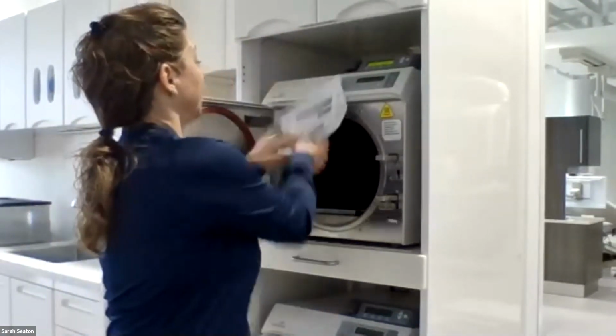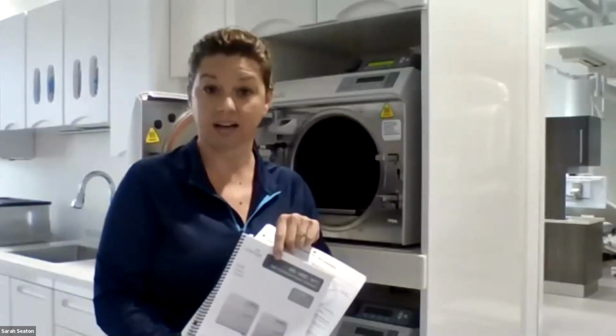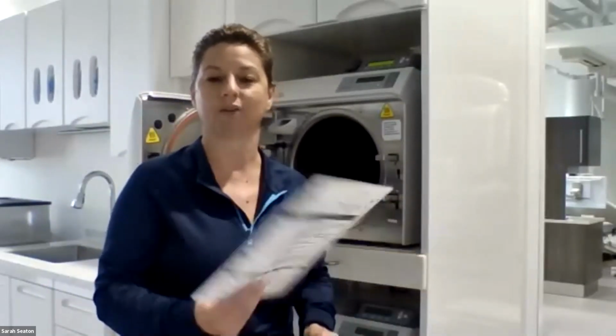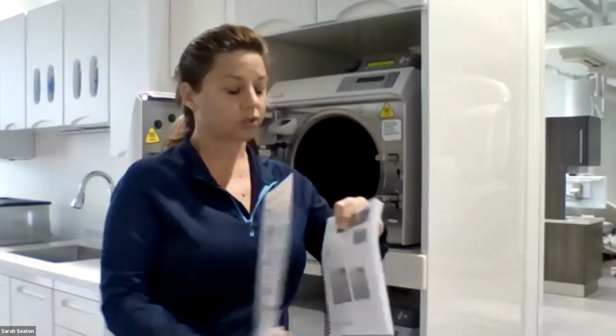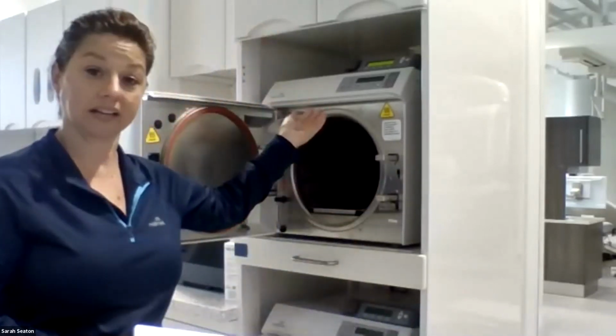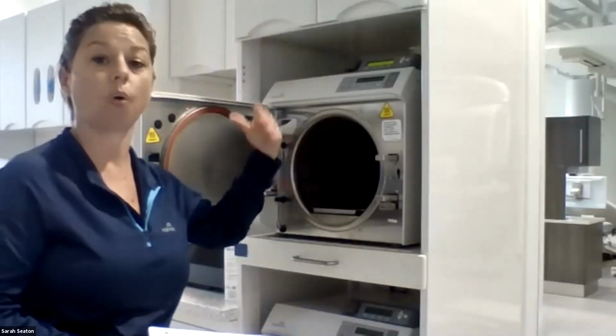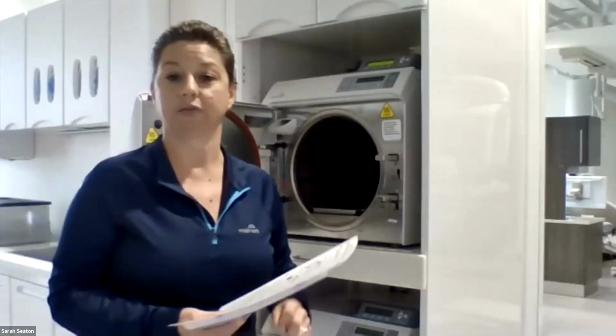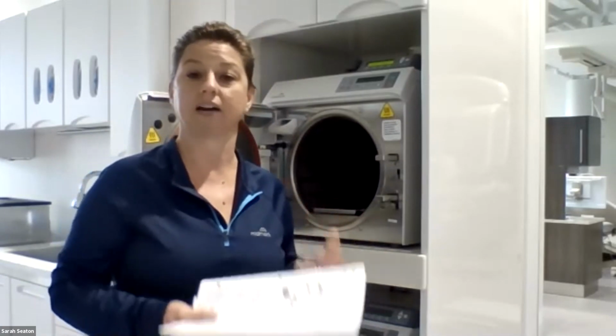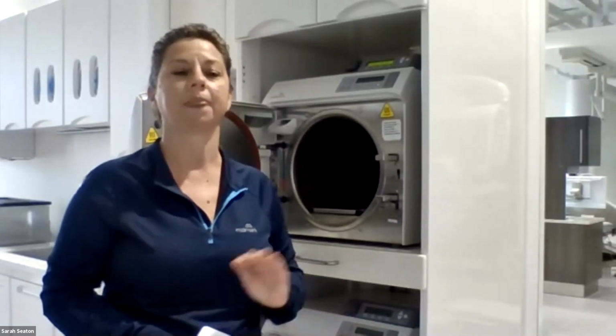With each sterilizer, you get an in-depth user guide, and you also get this quick reference use guide. So, maintenance: when and how. Fortunately, the sterilizer will tell you or remind you when. When is every 7 days. It's going to remind you it's time for weekly maintenance. On the 28th day, it tells you it's time for a much deeper monthly maintenance. We're just going to step through that real quick.